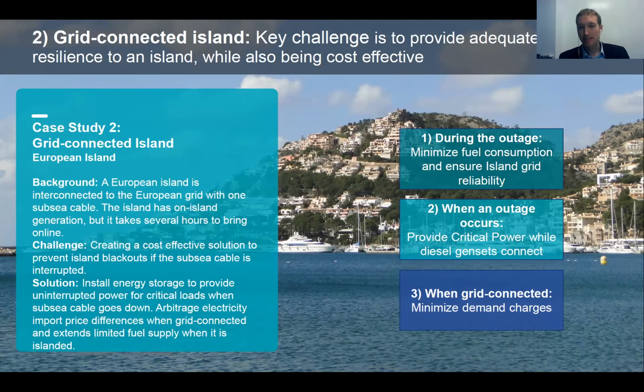So when thinking about a backup plan, the solution is a battery that can provide a bridge while the island gets its own generation up and running. The battery provides power to critical loads like hospitals and banks for several hours while diesel engines are started. Because the battery can charge and discharge very rapidly, you can bring the on-island diesel gensets up much more quickly, since they don't have to worry about synchronizing to the grid or frequency issues — the battery handles that.